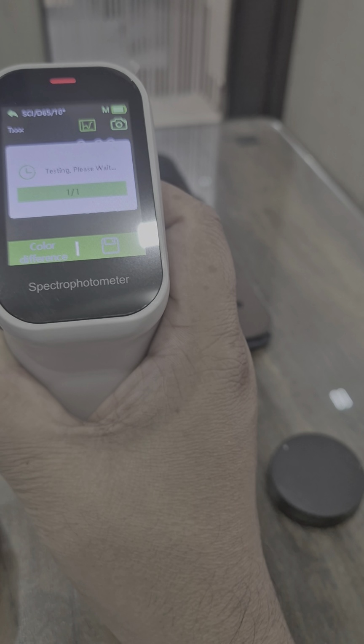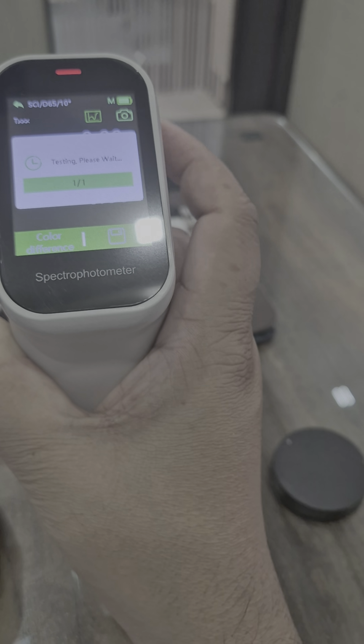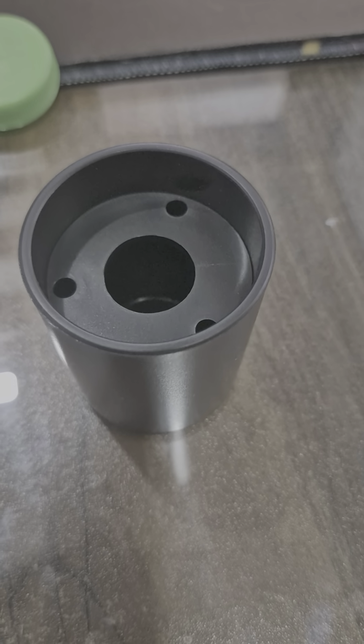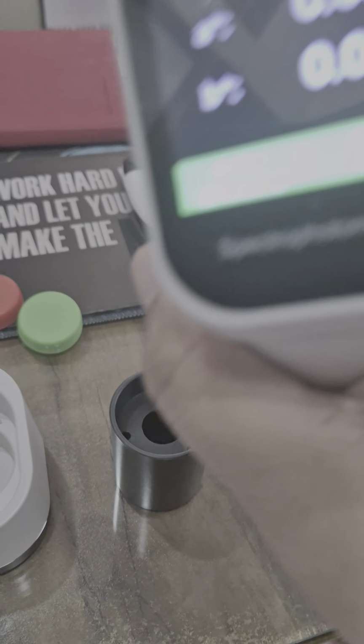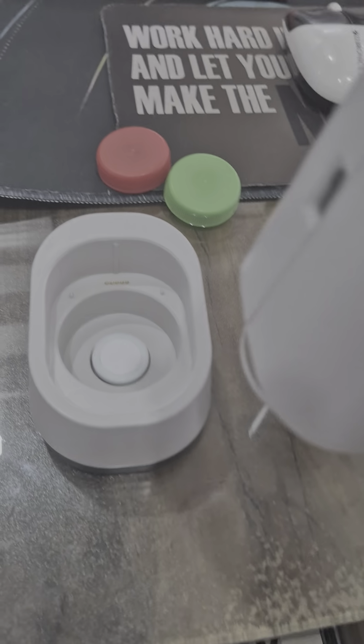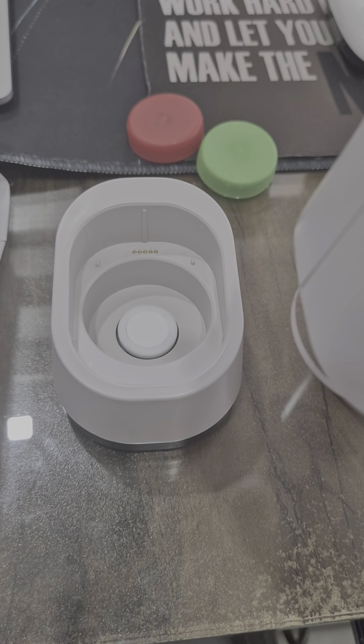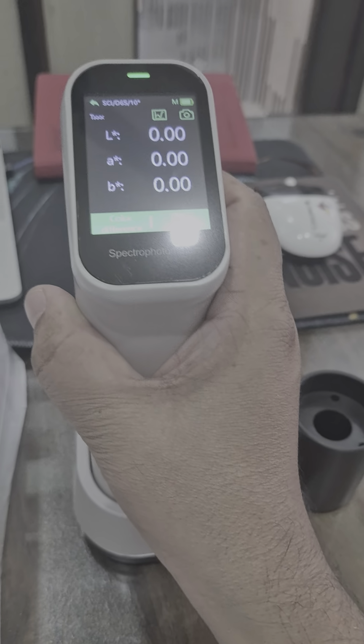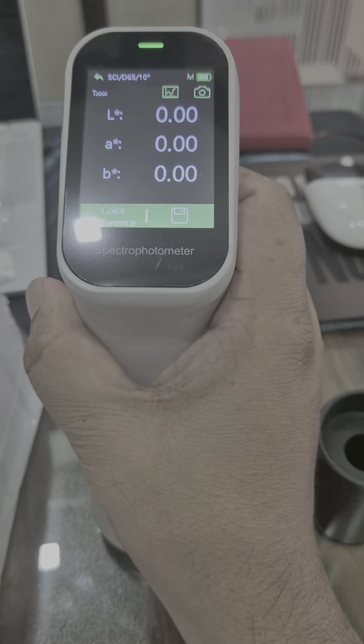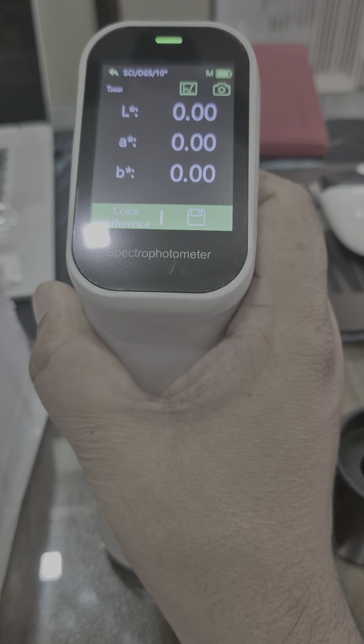It is showing 0. Why is it showing 0? Because it has 0 air and there is no reflection. So calibration is done like 0 or high reflect. High reflection is about 100, max 100 L value. Our tile value is approximately 98 point something. So I'll just take readings.